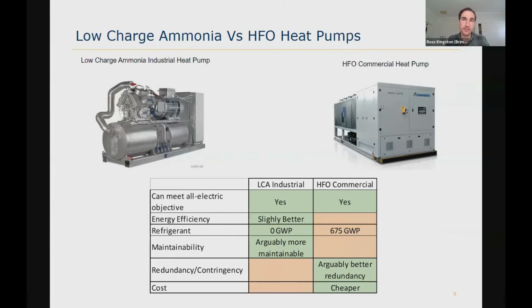Unfortunately, we ended up with a synthetic refrigerant HFO commercial heat pump in the end. There's a few different pros and cons in favour of each technology, but in a nutshell, the ammonia heat pumps were too expensive and perhaps a bit too hot to handle for the engineers and builder we'd already engaged by the time we got to the all-electric decision. There's a bit more complexity, a bit less able to be bought off the shelf like the commercial heat pumps are, and a bit too much rework into the building envelope required.